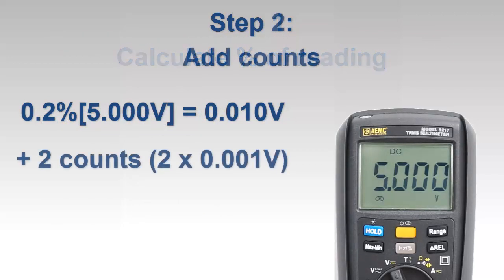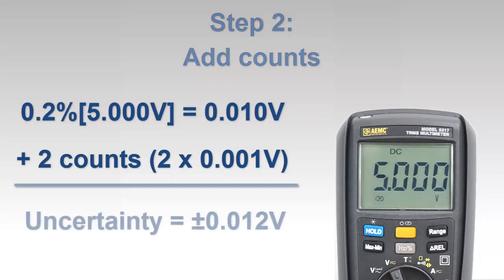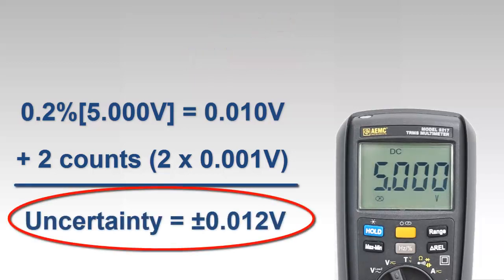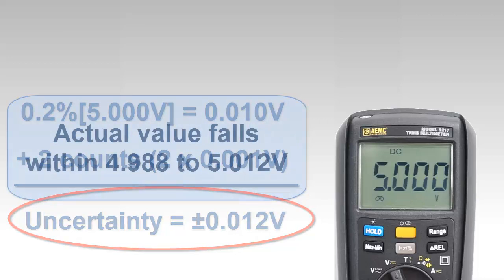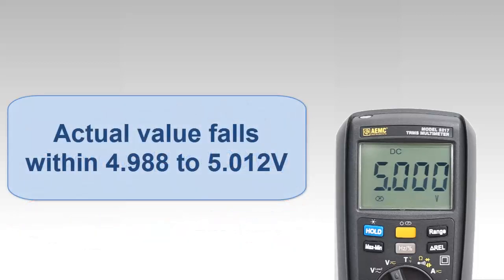We then add two counts. Taking the least significant digit of our reading, we define each count as one-thousandth of a volt. Thus the sum of the two counts equals 0.002 volts. Adding the percentage and counts together, we calculate an uncertainty of plus or minus 0.012 volts, or twelve thousandths of a volt. Thus in the example shown on the screen, the actual value falls within the range of 4.988 to 5.012 volts.